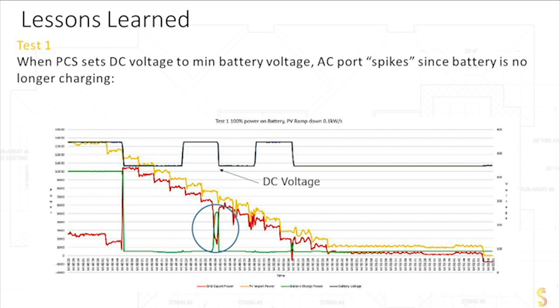So the PCS or the inverter sees, oh, the battery's trying to charge, it's dropping my red line way too close to zero, I don't like that, we don't allow that, it violates the golden rule, so guess what, I'm turning your voltage off again. And so the voltage drops once again for the second time to a threshold that the battery cannot operate at. And as a result, the battery turns off, which is why the green spike comes right back down, and why the red line jumps right back up. And again, it goes through another clearing time and the whole process repeats.